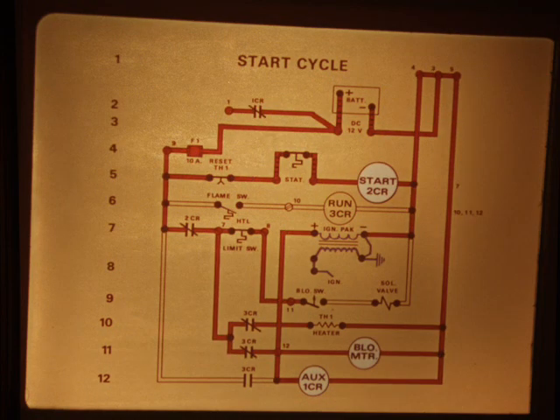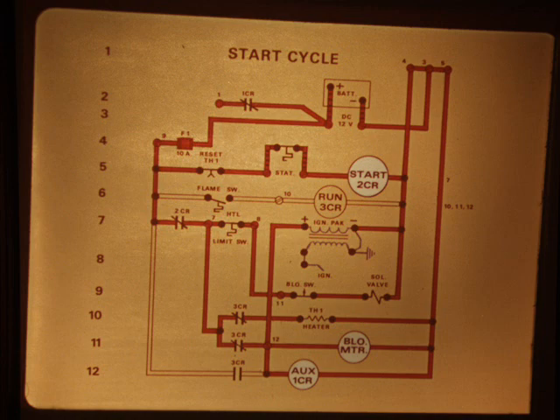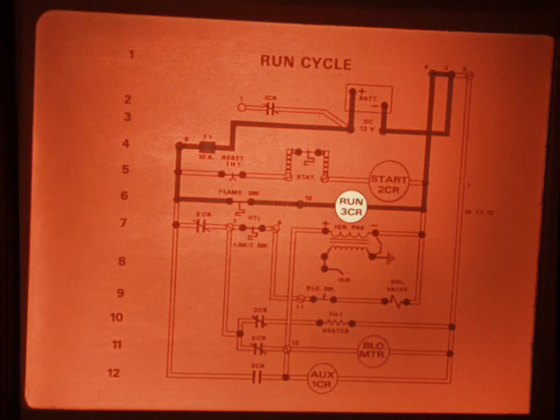Power also goes through the run relay, which is normally closed, to the heater in the thermal reset relay, to the ignition pack, to the auxiliary blower relay, and to the blower motor. Then the blower starts to run. When the blower reaches a certain speed, the centrifugal switch closes to energize the gas valve solenoid, and the furnace fires. That's the start cycle. The run cycle begins about 10 or 15 seconds later, when the flame rod warms up and closes the flame switch. This energizes the run relay coil.